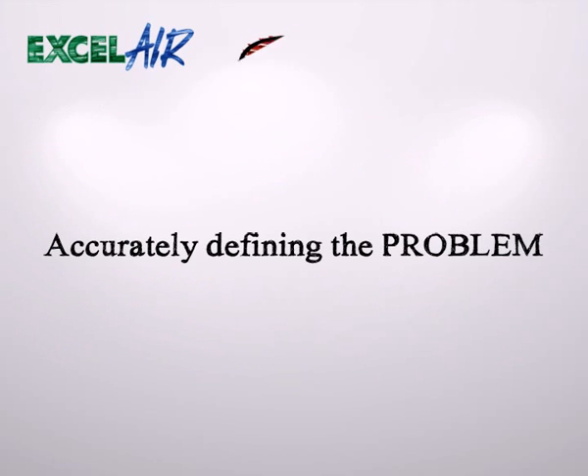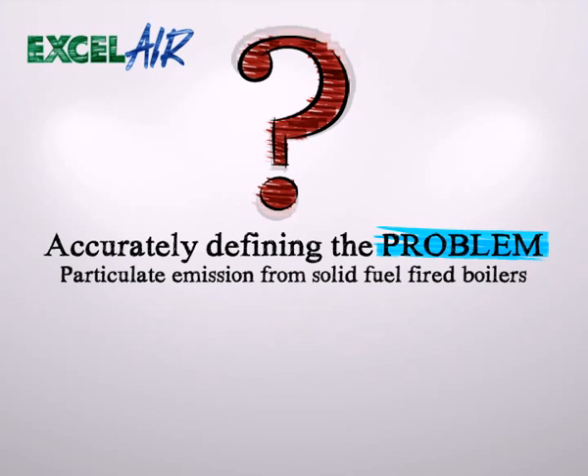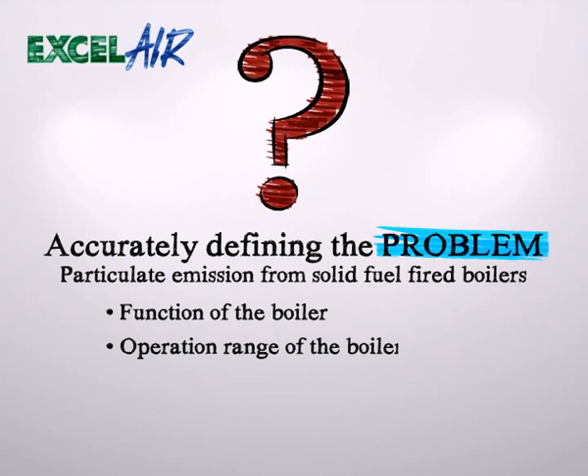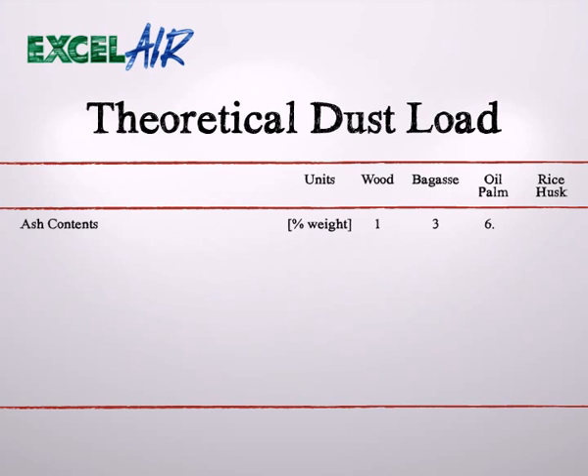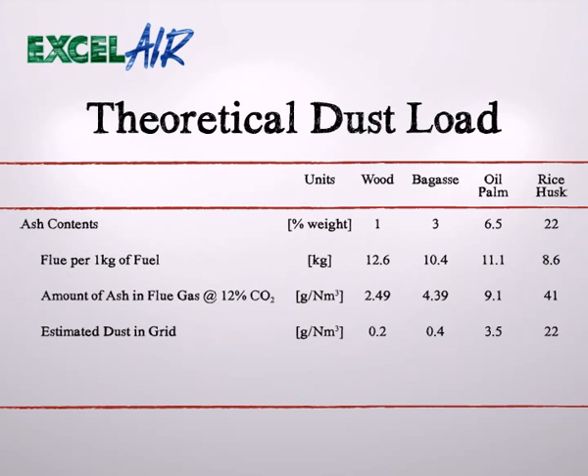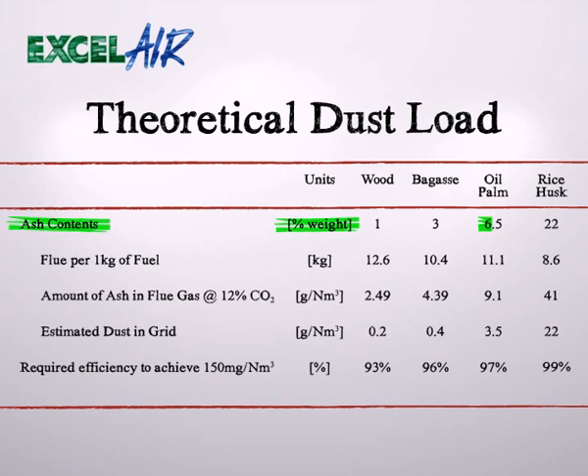To accurately define the problem, we have to know and understand the following: the function of the boiler, the operation range of the boiler, fuel consistency, and variations in flue gas conditions. The concentration of dust in the flue gas depends primarily on the ash content of the fuel. Different fuels have different ash contents, so in order to design our dust collector, we need to know what type of fuel will be used.